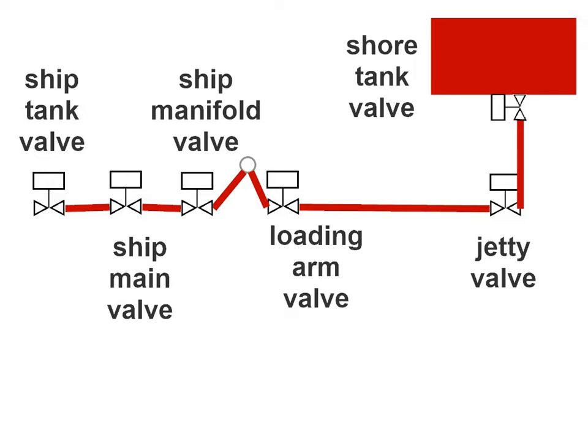Sudden pressure increases, or surges, are an undesirable condition in liquid transfer. Pressure surges can cause pipeline ruptures. The ESD system stops the transfer pumps and closes the main valves with the particular sequence and timing.